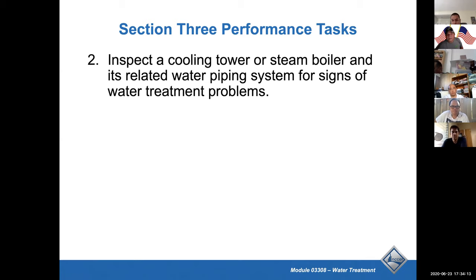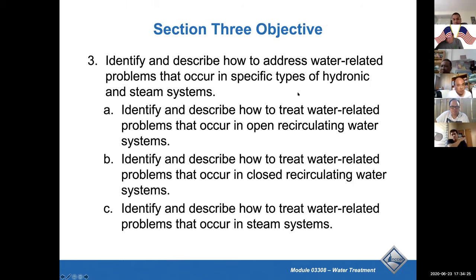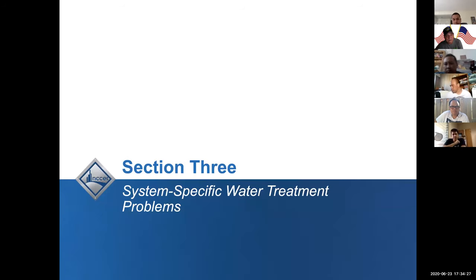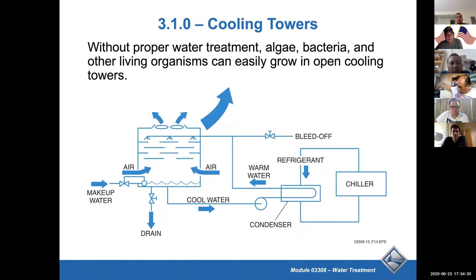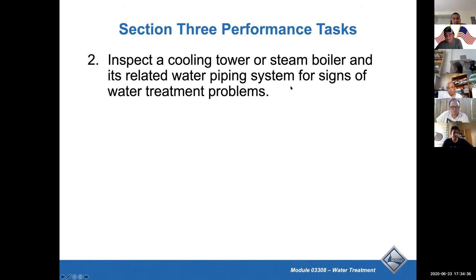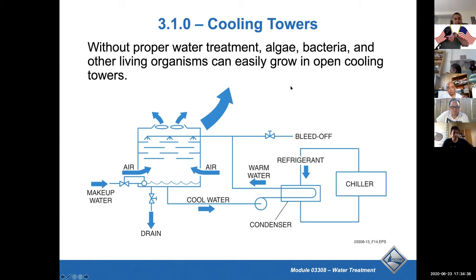We don't use a lot of steam heating, okay? Inspect a cooling tower, a steam boiler, and water pipes for signs of water treatment problems. You can actually see problems in the water system by just doing a visual inspection.